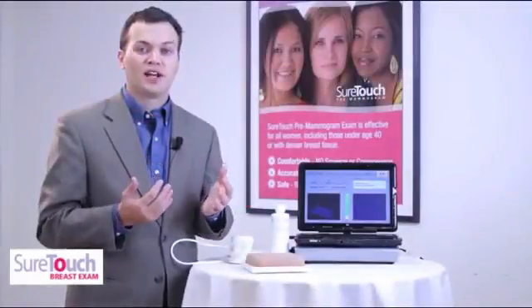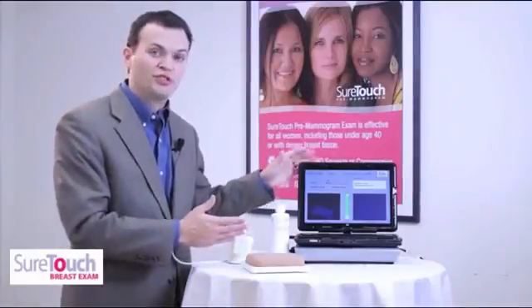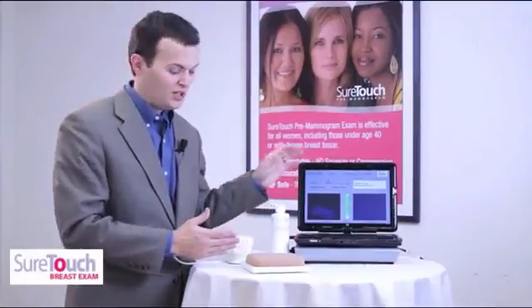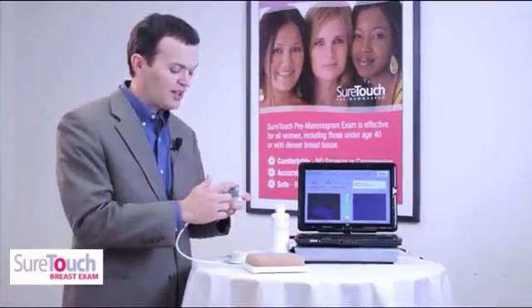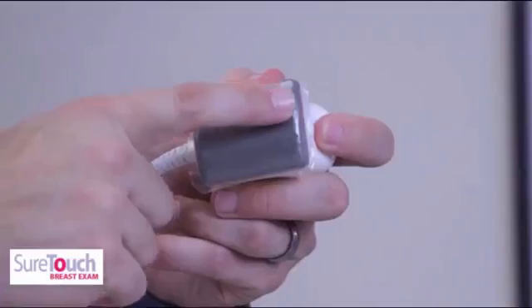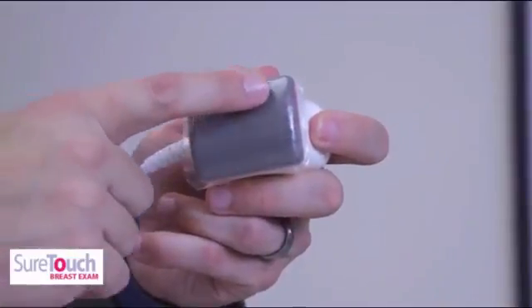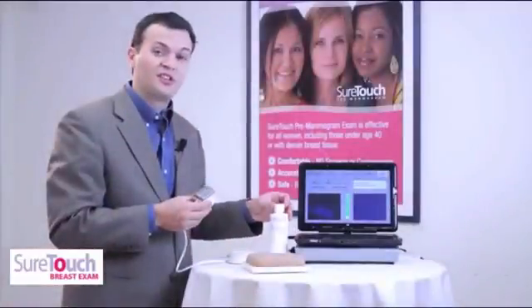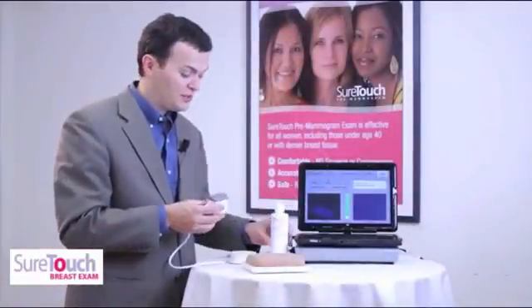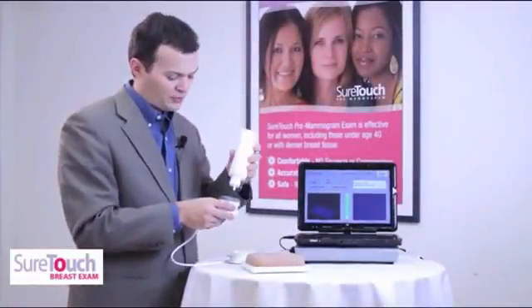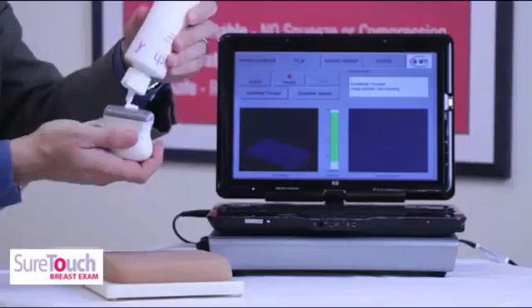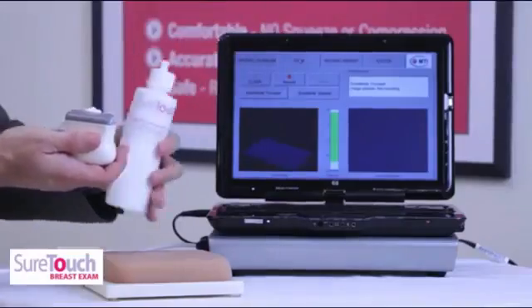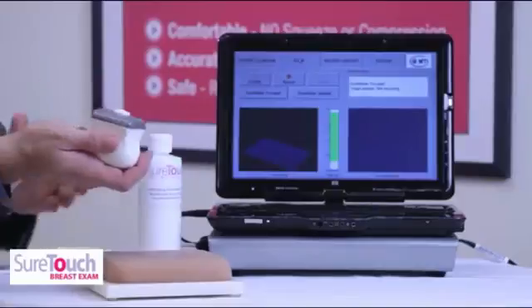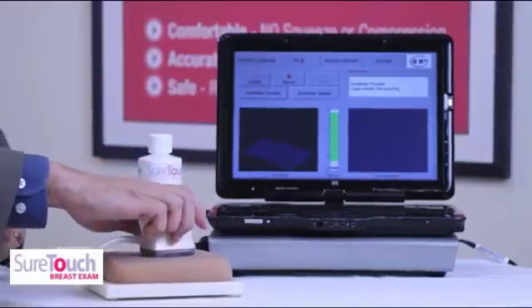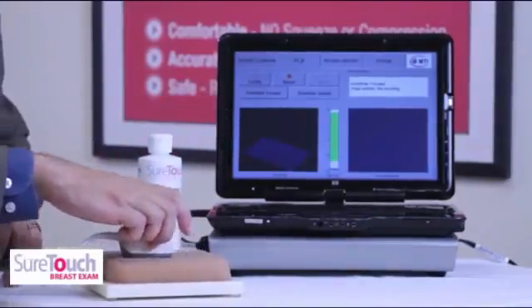PPS worked with Medical Tactile to develop SureTouch, which is powered by PPS TactArray technology and uses a hybrid TactArray sensor mounted on the end of this probe to image lesions found in the breast. Here, I'm going to demonstrate using the simulated breast tissue called a phantom, which is provided with the SureTouch for calibration and training purposes. I'll apply some of the lubricating lotion, and now I'll press the probe into the phantom as we watch the response pressures here on the screen.